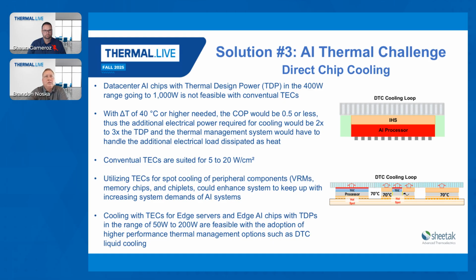Historically, without liquid cooling—just high performance air cooling—it was limiting what you could do in these hybrid systems. But now with direct to chip liquid cooling, whether water only or pumped two-phase systems, the capacity of those systems to move and manage heat locally is enabling other configurations where we can leverage the parameters of the TEC to manage heat from other peripheral components.